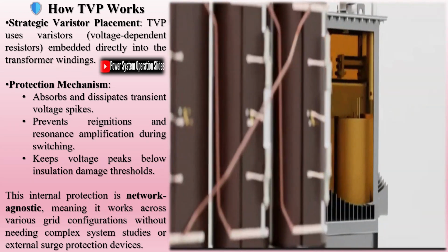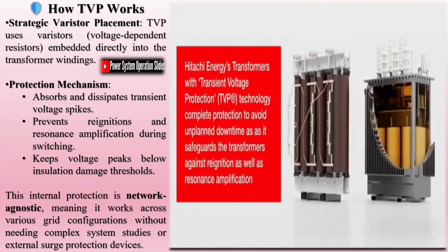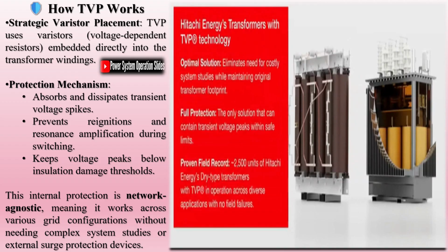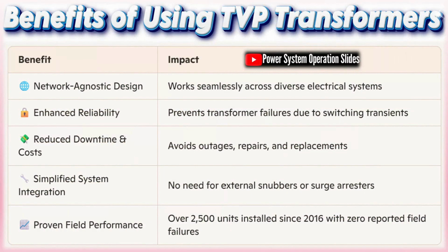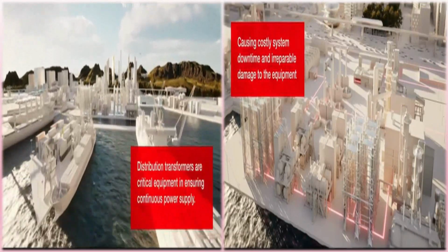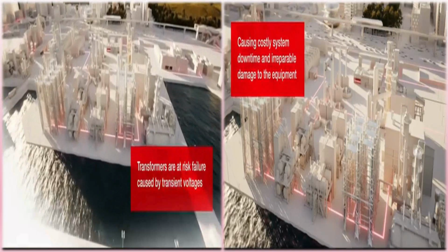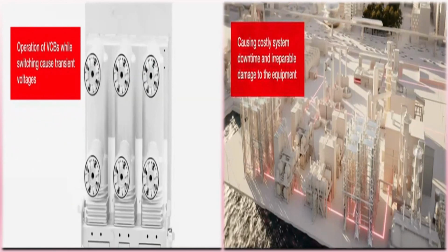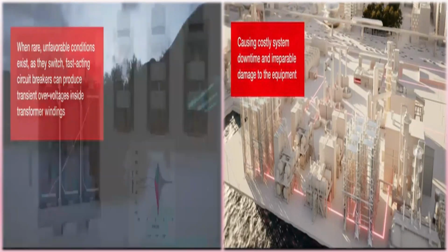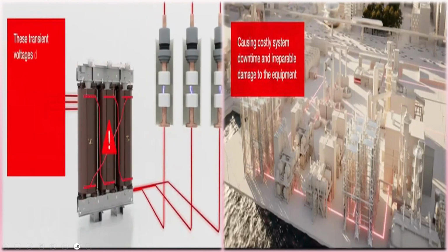Strategic varistor placement. TVP uses varistors, voltage-dependent resistors embedded directly into the transformer windings. Protection mechanism: absorbs and dissipates transient voltage spikes. Prevents reignitions and resonance amplification during switching. Keeps voltage peaks below insulation damage thresholds. This internal protection is network agnostic, meaning it works across various grid configurations without needing complex system studies or external surge protection devices.